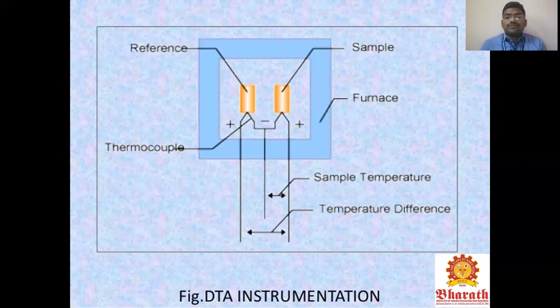The instrumentation for the DTA method: the sample holder, sample and reference cell, is made of aluminum. Sensors are platinum, or chromel-alumel thermocouples. One for the sample and one for the reference joint the differential temperature controller for the sensor. The furnace is an alumina block containing the sample or reference cells. Temperature controller program and furnace atmosphere also. Next one is the recording system.